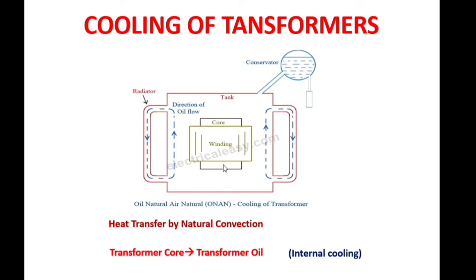Observe this two-dimensional sketch of the electrical transformer. Transformer cooling consists of internal cooling and external cooling. In internal cooling, during operation of the electrical transformer, heat is generated at the transformer core. The transformer function is to increase or decrease alternating current voltage. The generated heat is transferred to the surrounding transformer oil due to the temperature difference between the transformer core and windings and the transformer oil. Heat is dissipated from the transformer core to the transformer oil — this is about internal cooling, where heat is transferred by means of natural convection.